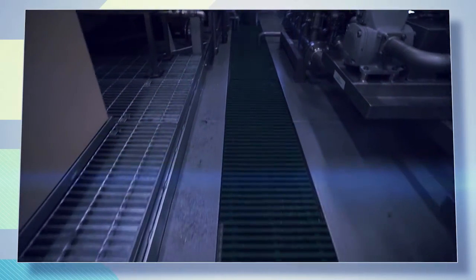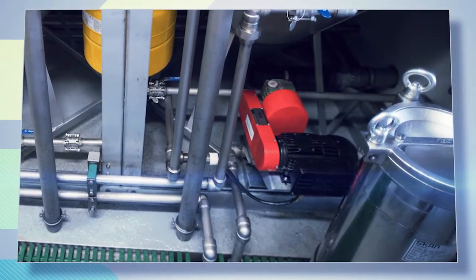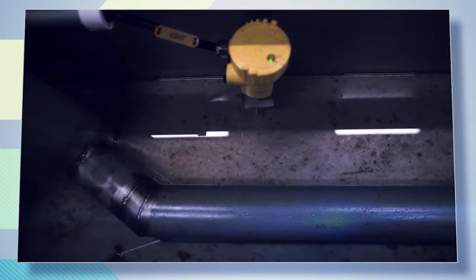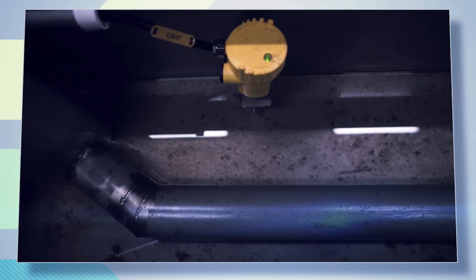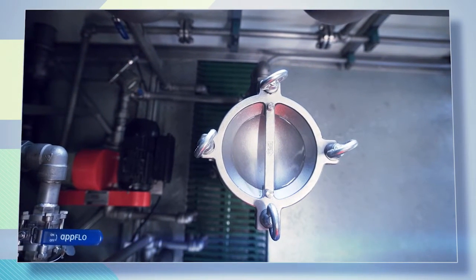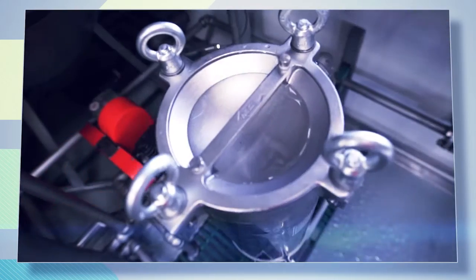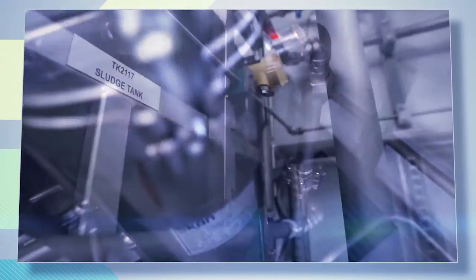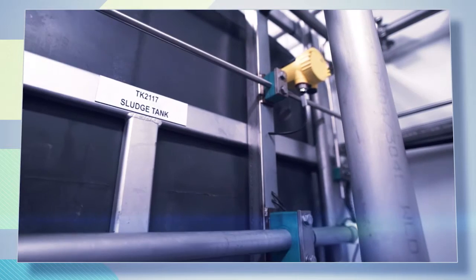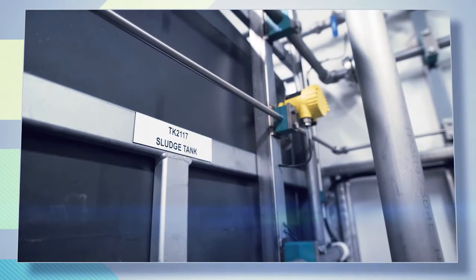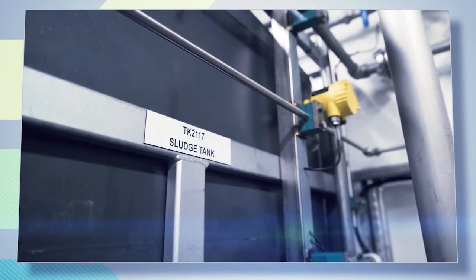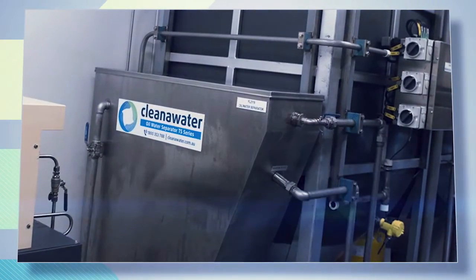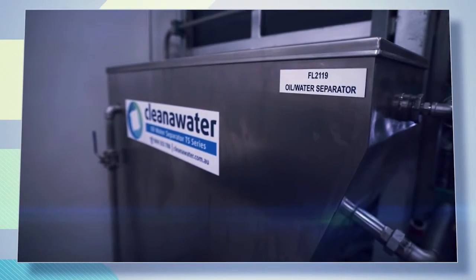Centrifuge waste and fluids recovered from the last chance filters are received in the common sump of the fuel block. A sump pump can be supplied to transfer fluids from the sump. A high-level switch operates the diaphragm-style pump automatically. Waste fluids and particulate can be processed in the fuel block. The waste is pumped through a bag filter to the sludge tank, where the fluid gravity separates into water and diesel. The diesel fuel can be recovered and treated in the centrifuges. The water phase is further treated in an oil-water separator.